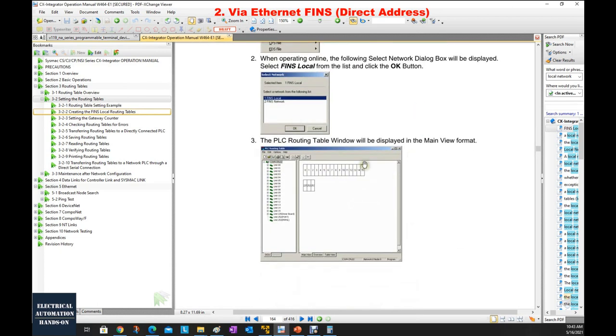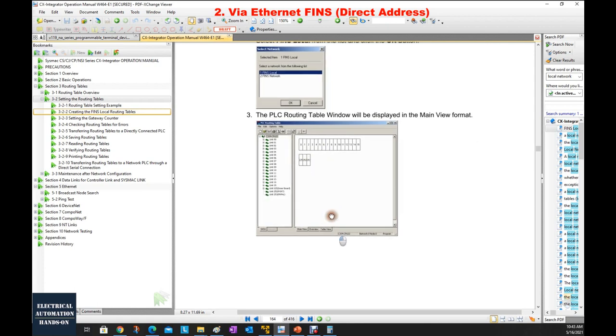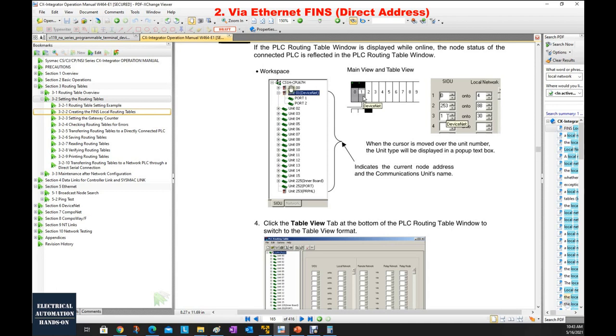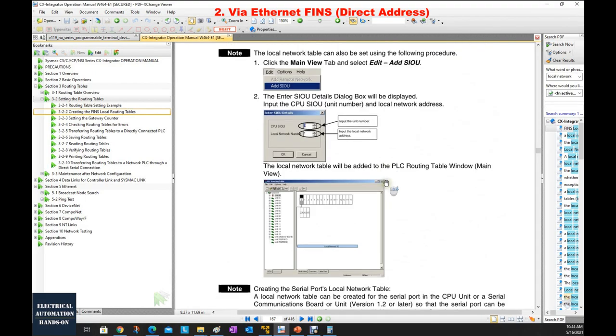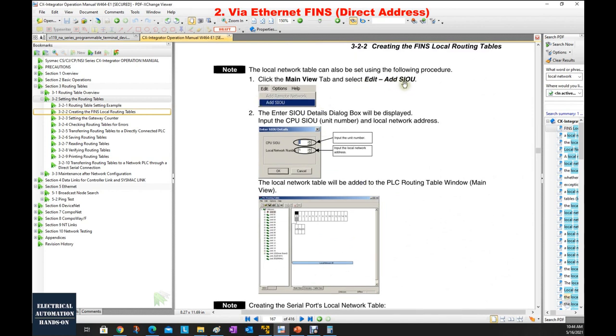To understand the procedure, find the CX Integrator Operation Manual and go to Section 3 — Routing Table, specifically Section 3-2-2: 'Creating the FINS Local Routing Table.' The main idea is to use the routing table to set up the network. Start the routing table, select FINS Local, and you'll find the configuration page. When you read from the PLC (upload), you'll see the actual unit numbers. In my case, the CPU unit number is 5. After uploading, you'll see the highlighted unit, and you need to right-click the unit icon and set up the network ID — adding a SIOU and setting the local network number to 1. After that, transfer this setting to the PLC.